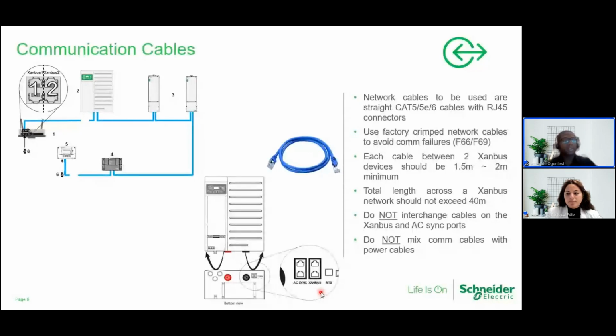Now the AC sync ports are only peculiar to the inverters, to the XW Pro inverters, I would say. You might see this on the Legacy XW Plus, on the Legacy XW also, but it's basically for the same function, for stability. You have two inverters, three inverters, a whole lot of inverters on that same network feeding the same load. You have to make sure that the system all starts together at the same time. When I'm talking about starting together, I'm talking about the sinusoidal function. If you remember your AC synchronization graph, the one that simply goes up and down like a sinusoidal wave, this is where the AC sync function is really going to come in handy.